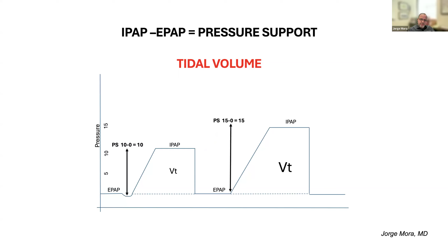When you're using a bilevel PAP ST, which stands for spontaneous and timed, the spontaneous breaths obviously need a trigger, because you're triggering it, hence the spontaneous part. That will trigger the ventilator or the respiratory assist device to deliver a pressure that will generate a flow and translate into a volume. And at some point, you're going to get a decrease in flow as the lungs inflate and there are recoil forces acting on it. That decrease in flow is what is going to define the cycling, and not necessarily the inspiratory time.